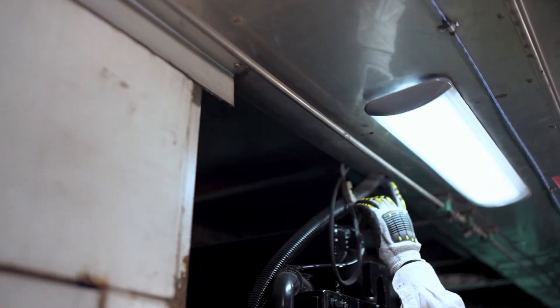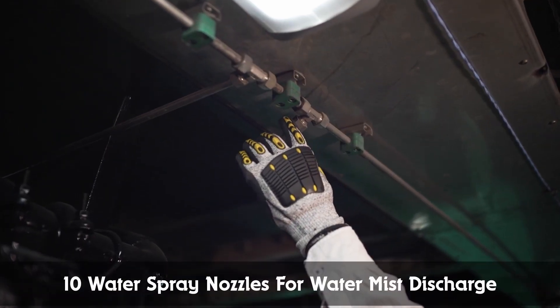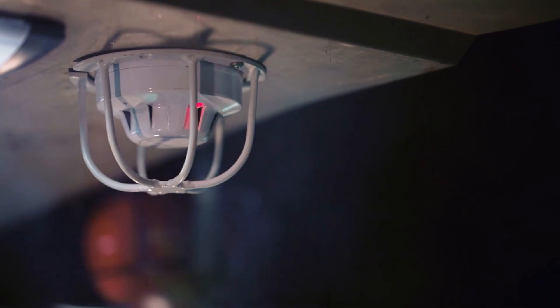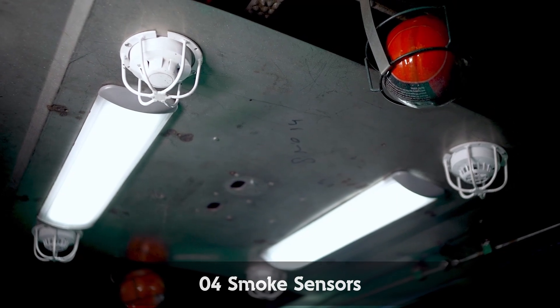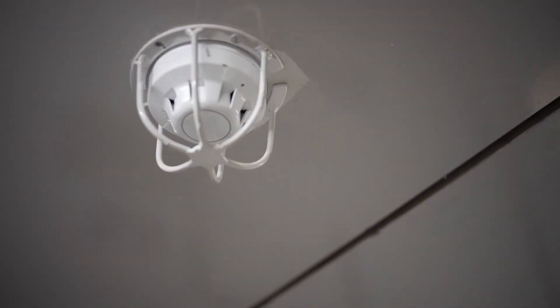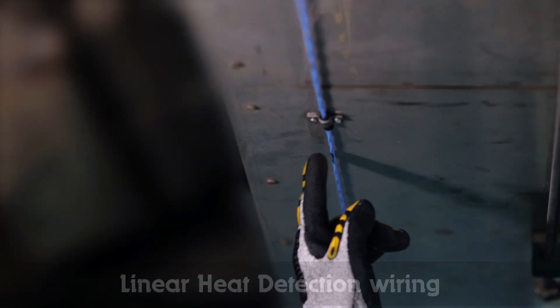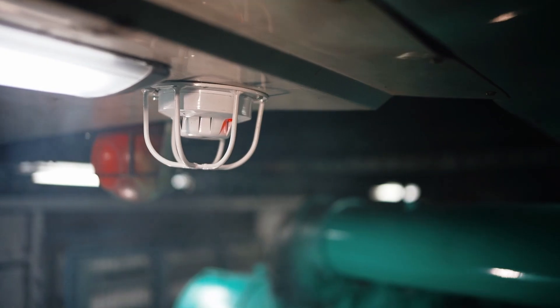The SS pipes branch out to the engine area. The system is equipped with 10 water spray nozzles for water mist discharge. It features smoke and heat sensors and an LHD system: four smoke sensors and two heat sensors covering the diesel generator, engine area, staff and guard rooms. Linear heat detection wiring is installed in the engine and luggage areas of the power car.